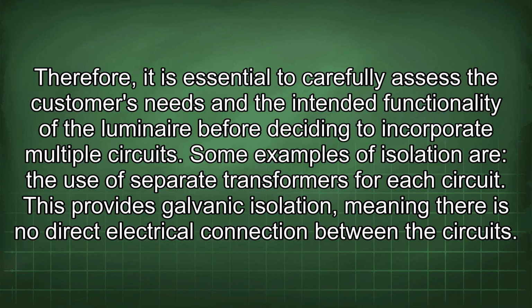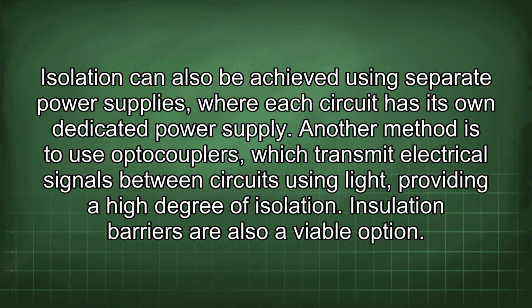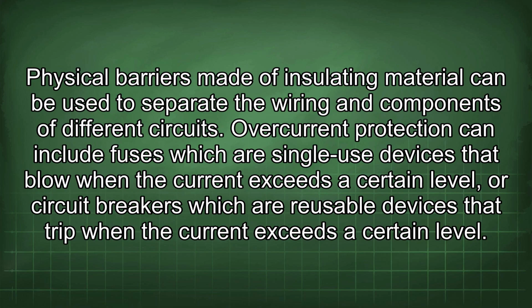This provides galvanic isolation, meaning there is no direct electrical connection between the circuits. Isolation can also be achieved using separate power supplies, where each circuit has its own dedicated power supply. Another method is to use optocouplers, which transmit electrical signals between circuits using light, providing a high degree of isolation. Insulation barriers are also a viable option. Physical barriers made of insulating material can be used to separate the wiring and components of different circuits.